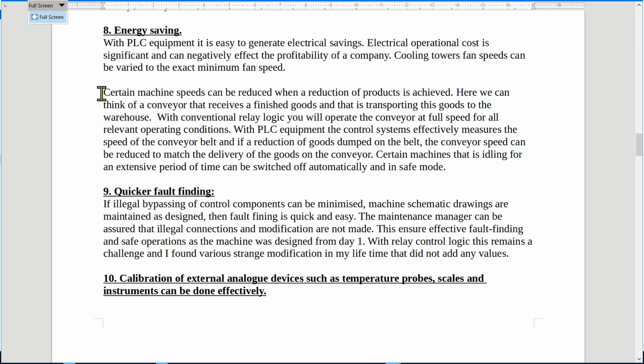Now, certain machine speeds can even be reduced when a reduction of products is achieved. In other words, if the products on the line is reducing, for example, conveyor systems, you can reduce the speed of the conveyor system to match the products that is being dumped onto the conveyor belt. Okay, here we can think of a conveyor that receives finished goods and is transporting these goods to the warehouse. With conventional relay logics, you will operate the conveyor at full speed for all relevant operating conditions. With PLC equipment, the control systems effectively measures the speed of the conveyor belt, and if a reduction of goods dumped on the belt is experienced, the conveyor speed can easily be reduced to match the delivery of the goods on the conveyor. In other words, less product on the belt, the slower the speed of the belt.